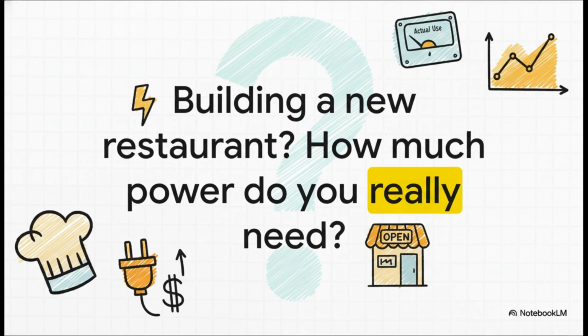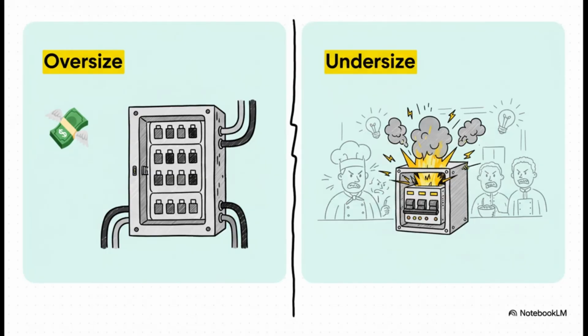It's Section 220.88. The title is literally Optional Load Calculation for New Restaurants. And here's the key. It lets you bypass that whole detailed Part 3 calculation. You just skip it. Well, you calculate the entire service or feeder load using just one table instead. Table 220.88. It's like the code is saying, look, we know new restaurants generally have predictable peaks, so here's a faster way. As long as it's a new restaurant installation, right? Exactly. That's the condition. So the big win here is simplicity, saving time.